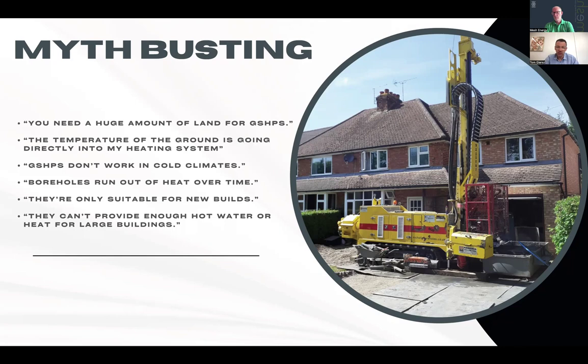If you install a 13 kilowatt heat pump and the heat loss of the property is 20, the heat pump has no chance to deliver this. It will work very hard, run all the time, and over-extract the heat from the boreholes, because the boreholes have certain running hours built into them. The more you run them, the less energy you can extract from them, because you are extracting all the time for a prolonged period. So the importance of the design is very high, to make sure the systems meet all the criteria for the heat load and demand of the property.